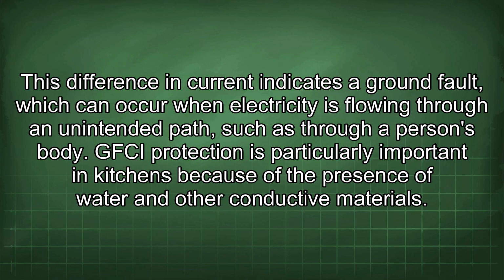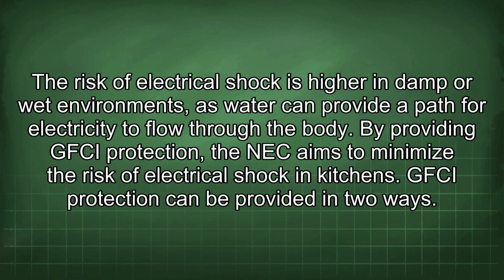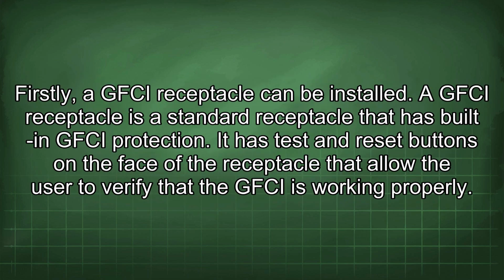GFCI protection is particularly important in kitchens because of the presence of water and other conductive materials. The risk of electrical shock is higher in damp or wet environments, as water can provide a path for electricity to flow through the body. By providing GFCI protection, the NEC aims to minimize the risk of electrical shock in kitchens. GFCI protection can be provided in two ways. Firstly, a GFCI receptacle can be installed.